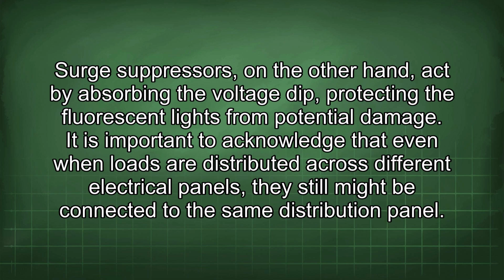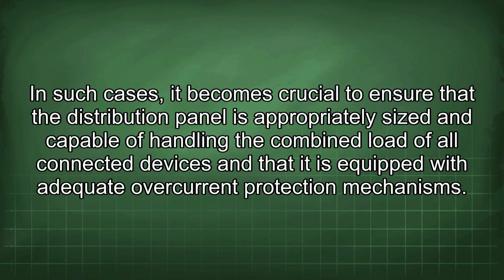from potential damage. It is important to acknowledge that even when loads are distributed across different electrical panels, they still might be connected to the same distribution panel. In such cases, it becomes crucial to ensure that the distribution panel is appropriately sized and capable of handling the combined load of all connected devices, and that it is equipped with adequate overcurrent protection mechanisms.